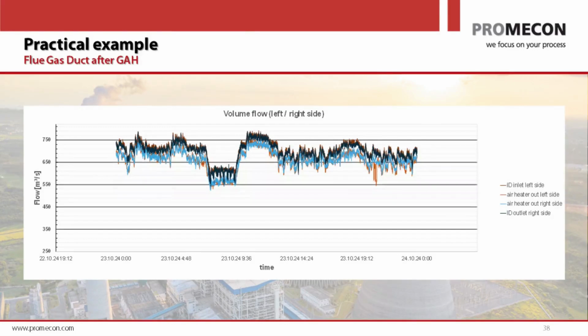As you can see here, a typical problem. You have the air heater out left side, air heater out right side. A little bit hard to see. The left and the right side, the blue and the red, and they are not really on top of each other. So we sometimes see differences in those flows, and that is usually an alarm for the customer. Is one of the sides pulling more ingress air? Ingress air is a big problem after the air heater, or are both sides okay? So it's a good indication also of maintenance requirements of your flue gas path.